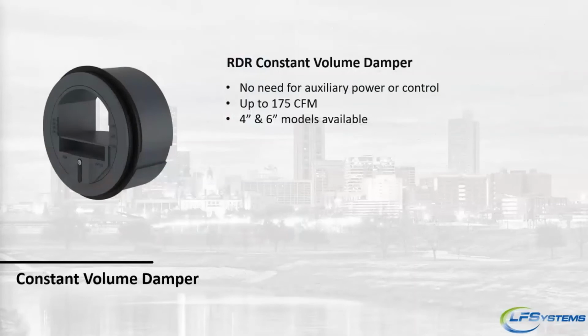One other component that we do want to talk about is constant flow dampers, or constant volume dampers, excuse me. This is a great option for bathrooms. Instead of using an individual fan, use constant volume dampers. Set the set screw to the flow rate that you want, and then it's just a spring-rated damper blade that will adjust based on the flow that's needed. So again, it's a great option to drop the cost on your bathroom exhaust.